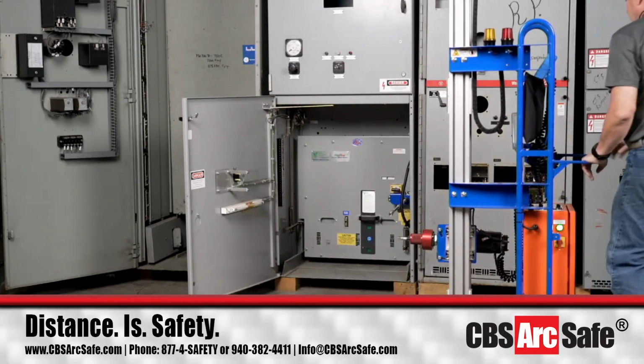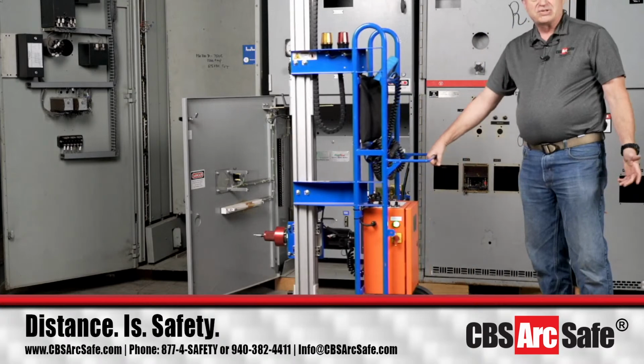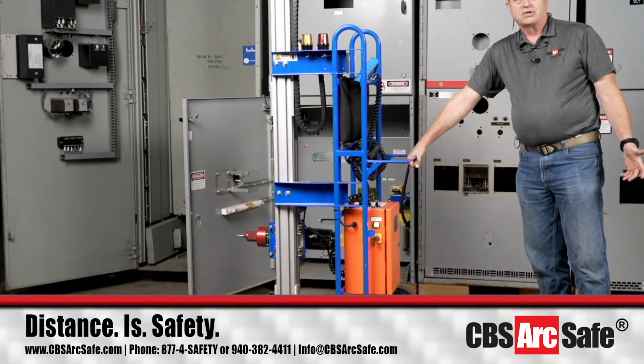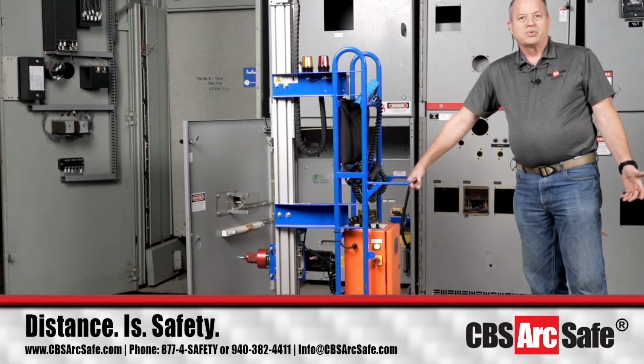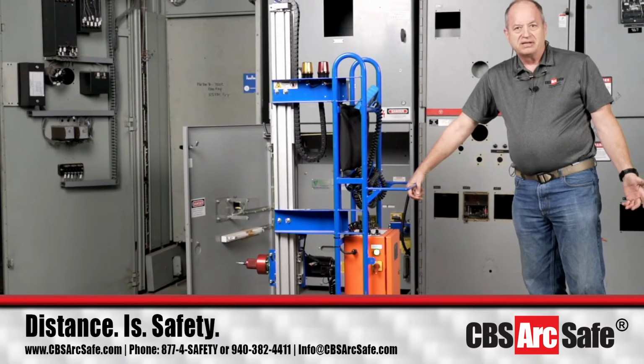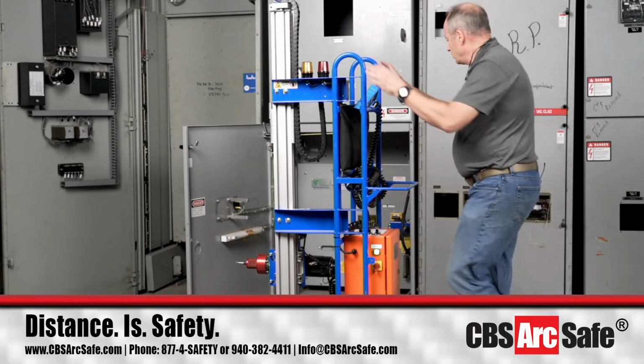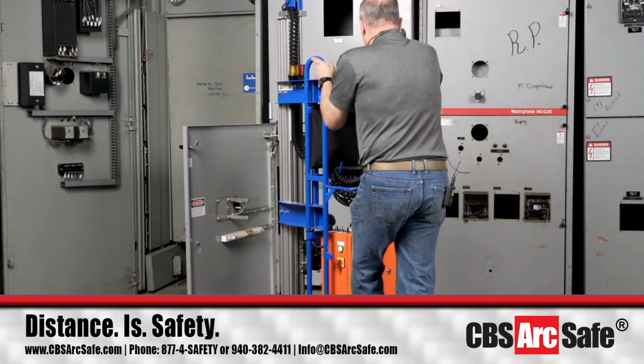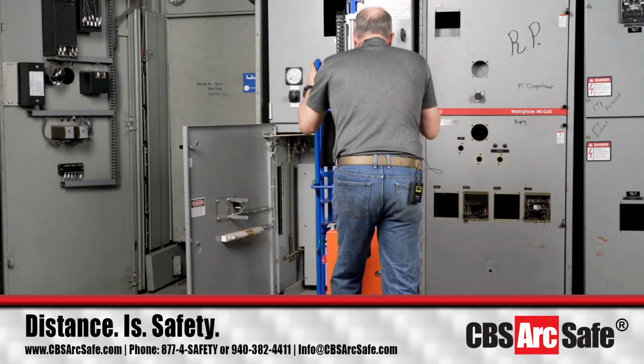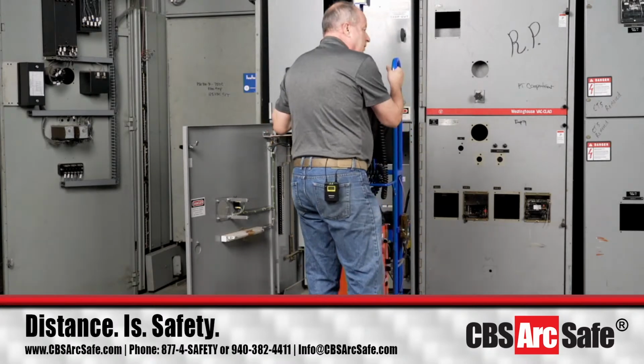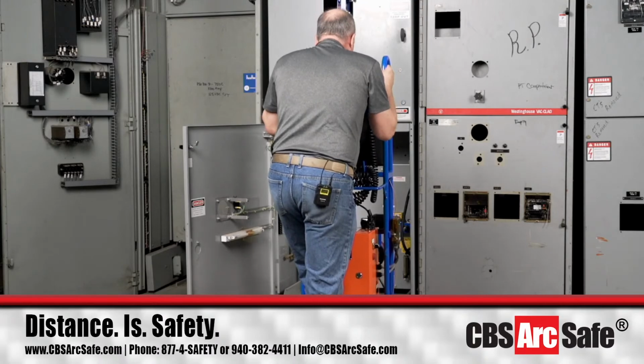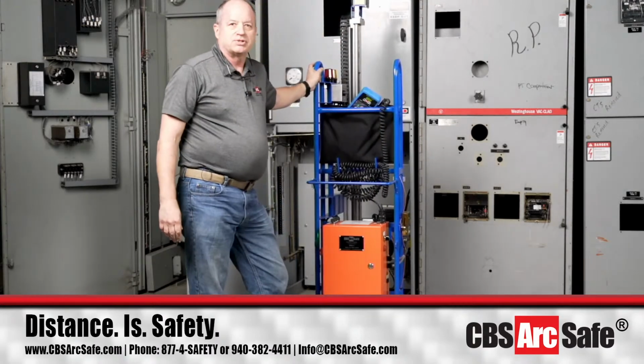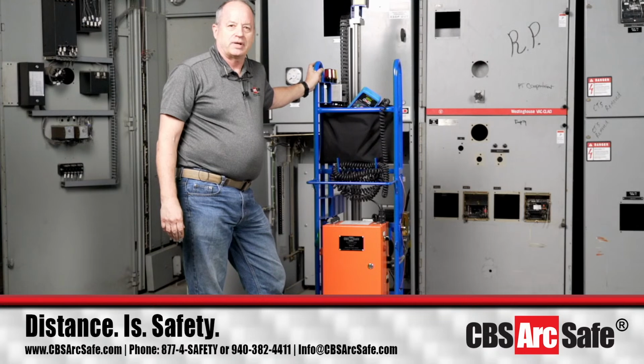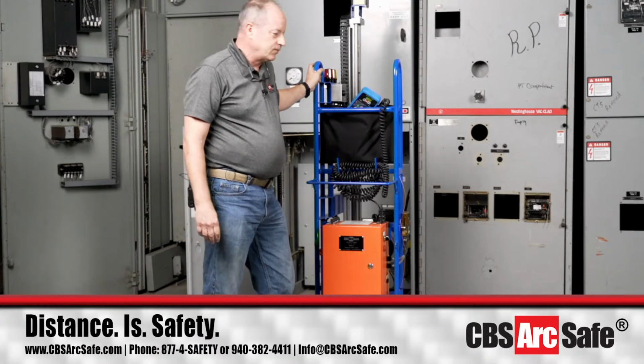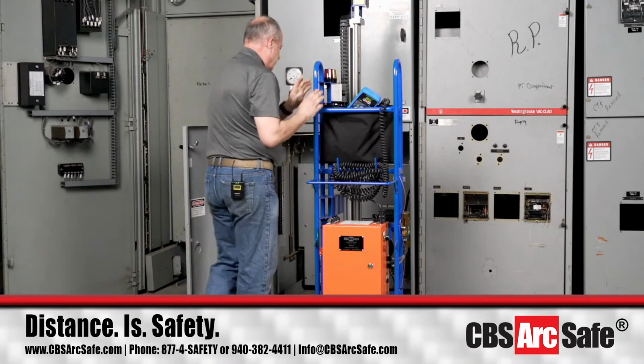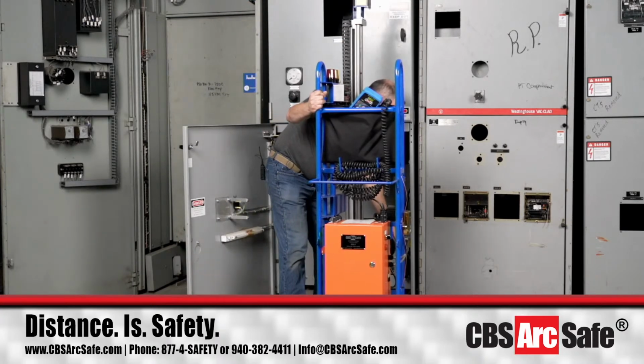Some of the things to note also is for our domestic customers, when you're dealing with breakers that go up to about 15 kV, the RRS-1 is only going to travel about 10, maybe 11 inches. When you get to some of the IEC breakers that are out there, the most we've seen a circuit breaker move with a rotary type of racking mechanism is 21 inches, and with an extractor type mechanism about 47 inches. So we work to help you identify what it takes to do your particular type of switchgear.